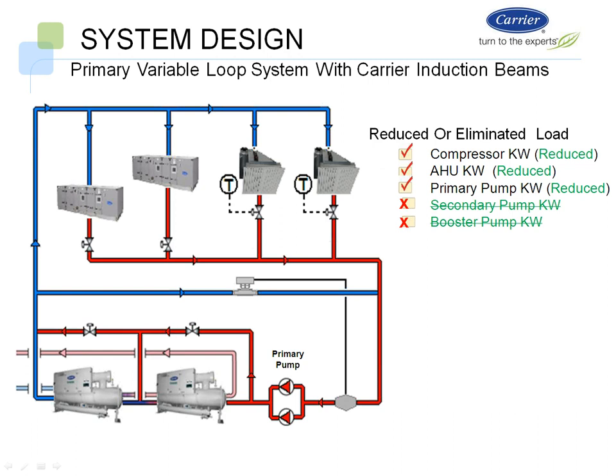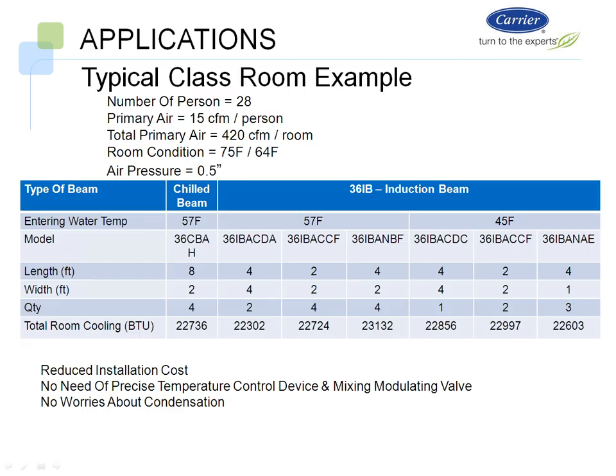Was there a comment? Mark, this is Ritesh, and the other thing I wanted to mention is when you're working with 58-degree water versus 42 or 45-degree water, just look at the number of beams required for a given zone or for the same duty or the same BTUs. Your initial cost on the beams goes down because now you can do 42, 45-degree water, so you get more cooling out of the cooling coils, and at the same time, you reduce the number of beams, installation cost, and everything in that case. Correct. Thank you, Ritesh. You brought me right to our next slide.